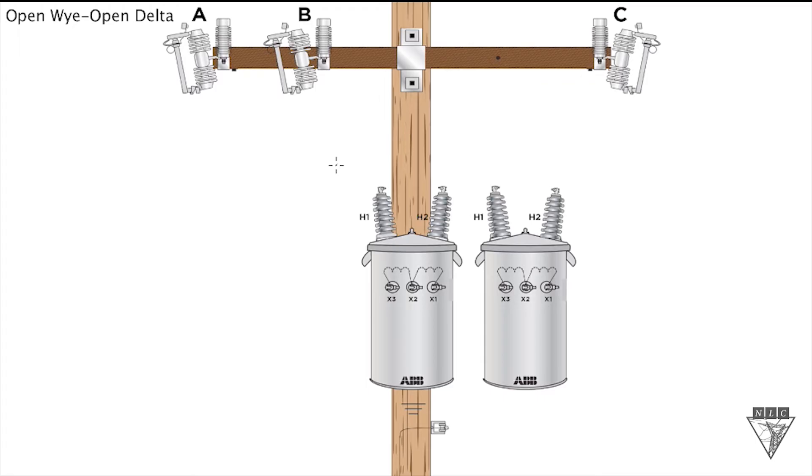All right, let's talk about an open Y open delta connection. Let's start on our primary side, and the first thing with this open Y primary connection is take your H2 bushings, tie them together, and then tie it to ground.